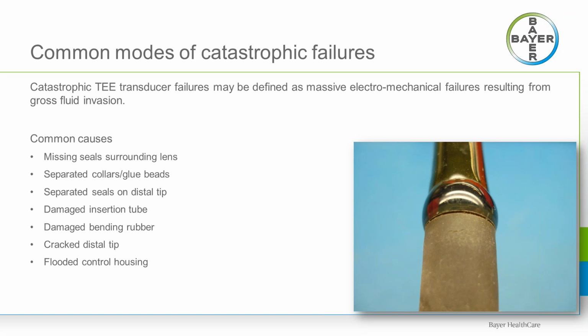The distal tip is typically composed of several plastic components which are adhered together to, again, form a watertight seal. Over time, or in combination with trauma, the collars can and will begin to separate from the tip or the tube, and the seams in the distal tip can also separate, and that in turn allows fluid entry during use, during gross cleaning, or disinfection.